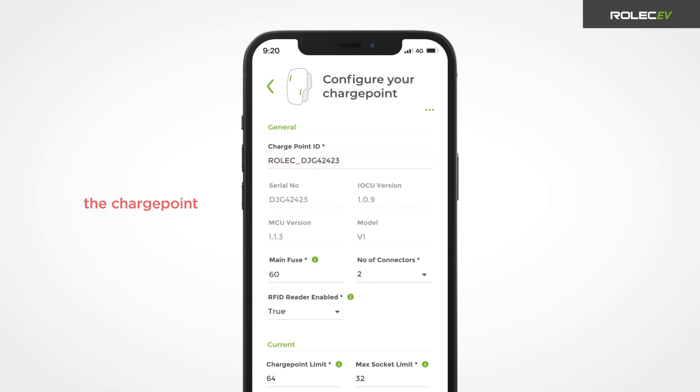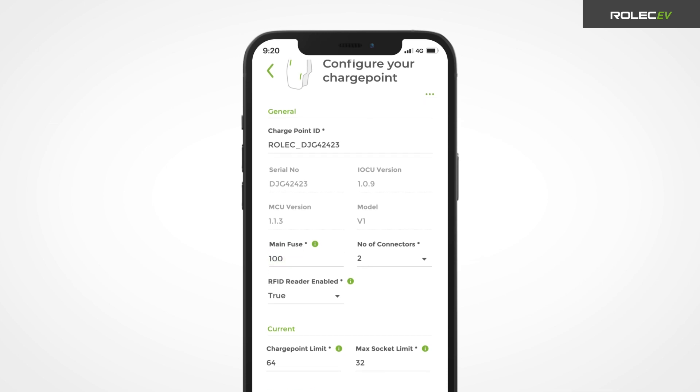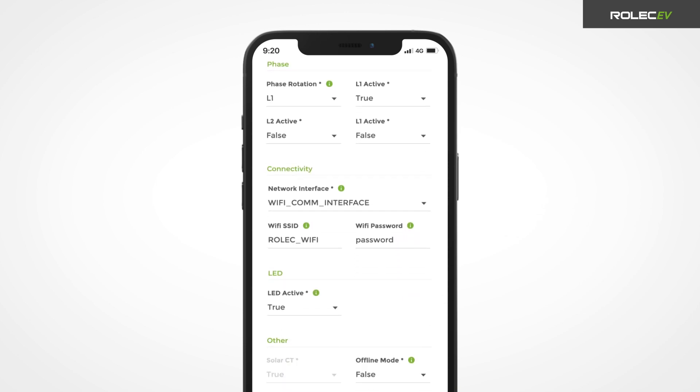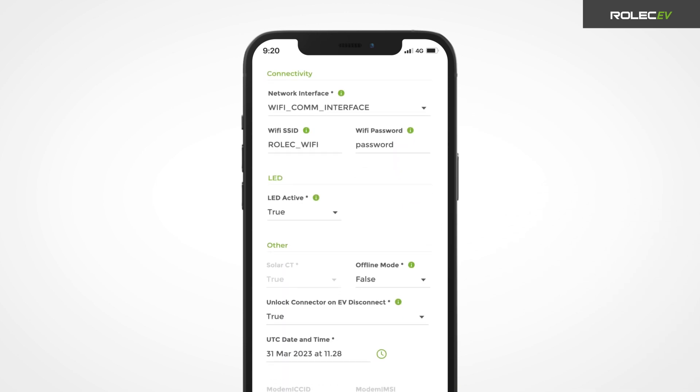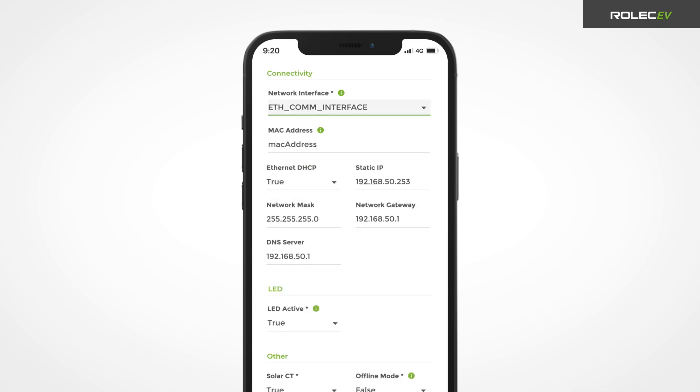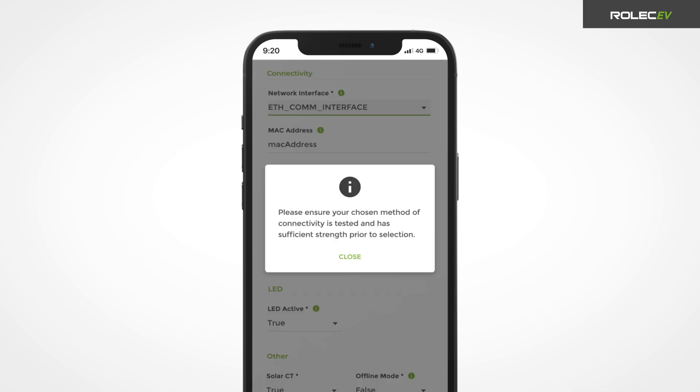If you have installed a load balancing CT clamp, make sure to input the correct rating for the main fuse for the load balancing feature to operate correctly. Enter the correct settings for the charge point, such as the number of connectors, the maximum charging output, and the chosen back office system. To connect the charge point to a network, open the network interface drop-down menu in the connectivity section to choose either GSM, Wi-Fi, or Ethernet and enter the relevant network information. For more information about any of the individual settings, press the i icon next to the setting to open a pop-up notification.